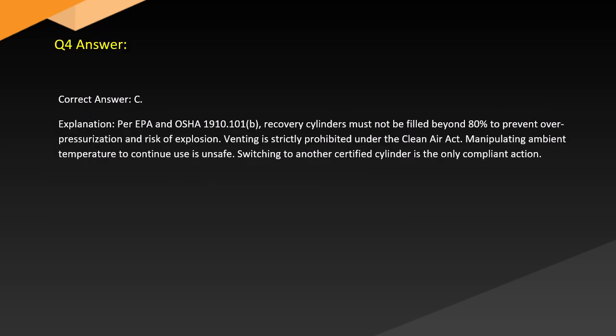Answer. Correct answer: C. Explanation. Per EPA and OSHA 1910.101(b), recovery cylinders must not be filled beyond 80% to prevent overpressurization and risk of explosion. Venting is strictly prohibited under the Clean Air Act. Manipulating ambient temperature to continue use is unsafe. Switching to another certified cylinder is the only compliant action.